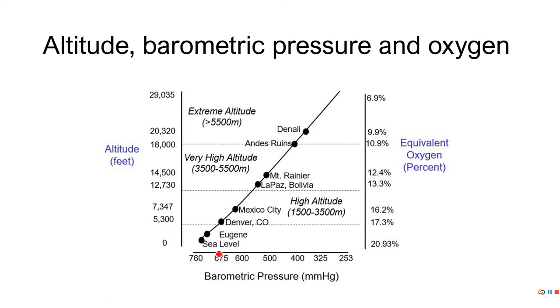Now if we had a lot of money and had a really, really fancy environmental chamber, what we would do is we just press some buttons and it would actually pull pressure. It would decrease the pressure inside the chamber. It would be called a hypobaric chamber, and that's all we would do, and we'd be able to simulate altitude in a hypobaric condition, which means less pressure. Those are very expensive. They do exist. They're really expensive. And so we have what's called a normobaric chamber.